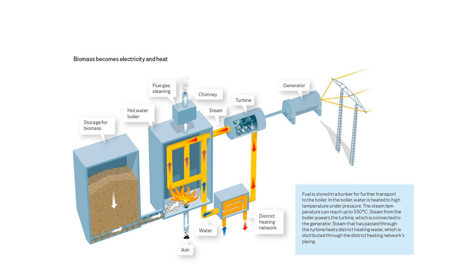Here is a model showing in brief the usage of bioenergy for producing electricity and heating. Fuel is stored in a bunker for transport to the boiler, where water is heated to high temperature under pressure, with steam temperature reaching up to 550°C. Steam from the boiler powers the turbine connected to the generator. Steam that has passed through the turbine then heats district heating water, which is distributed through the district heating network's piping.